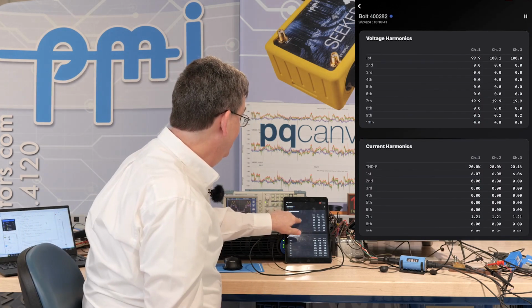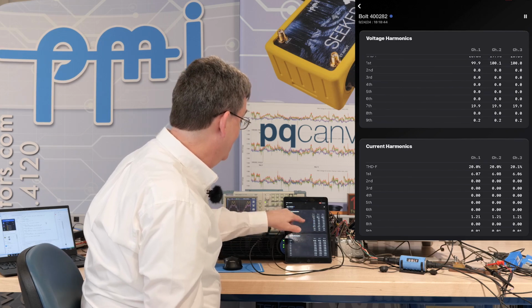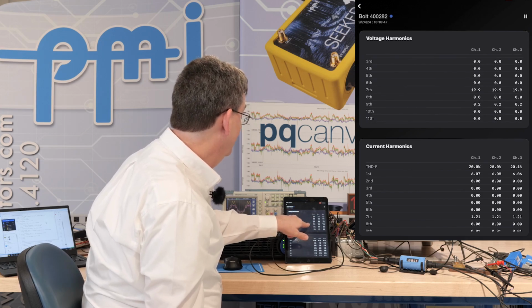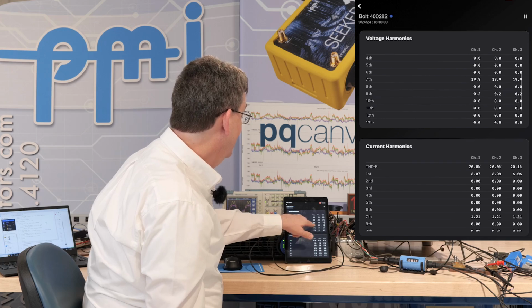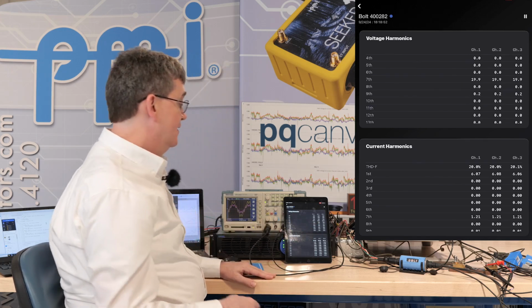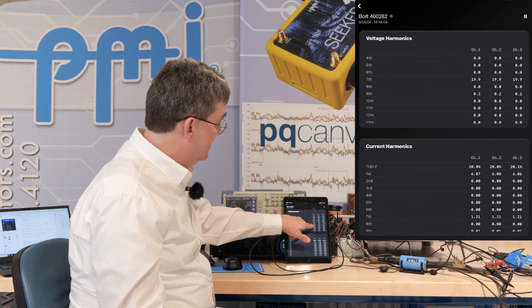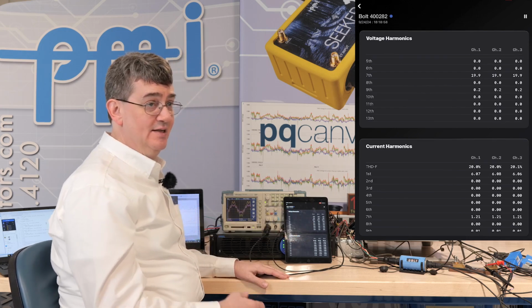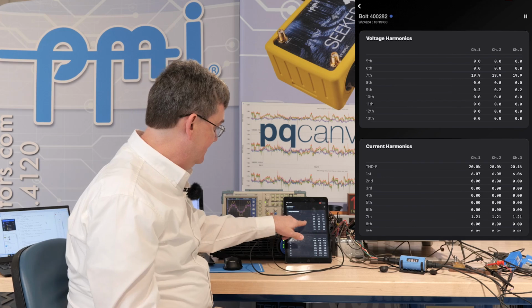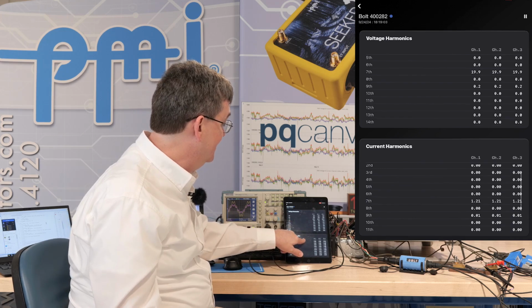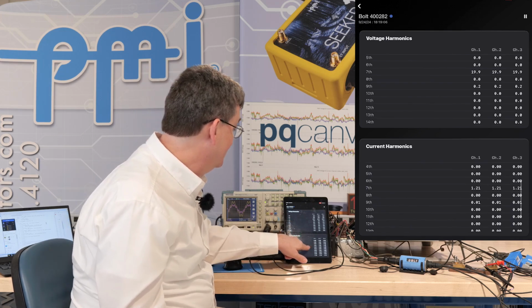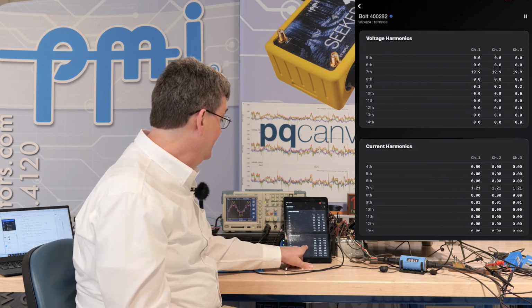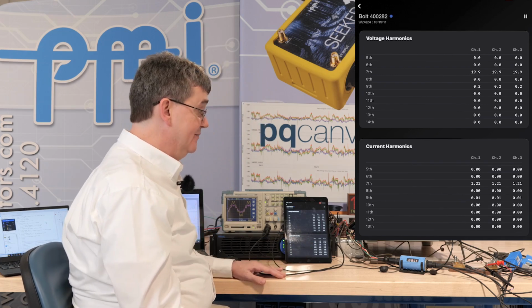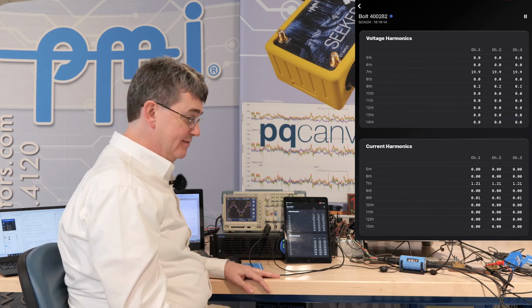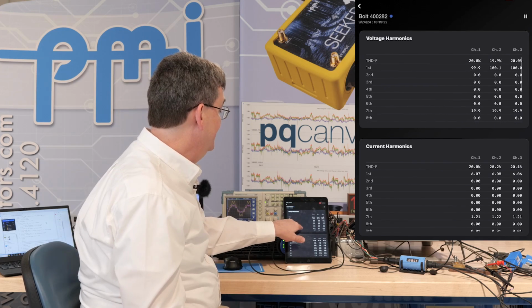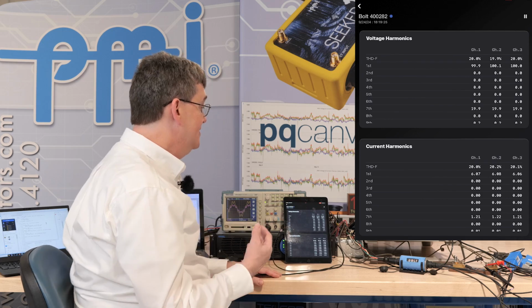And here on the meter screen, we see we have 100 volts at the 1st harmonic. We see 19.9 to 20 volts at the 7th harmonic, and the 9th harmonic is 0.2 volts. So even in the presence of other large harmonics, we still have good resolution down to very small levels for voltage, and for current we see the same thing. Proportionally, on the 7th harmonic we have 1.2 amps, and then on the 9th harmonic we have 0.01 amps, which is the correct value given that it's 6 amps on the fundamental. And we can also check the THD as a sanity check. It should be 20% THD roughly.